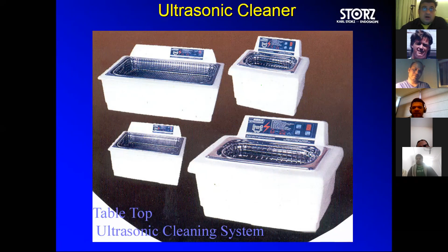Of course, there are ultrasonic cleaners now available. One can use them. Please mind you, these ultrasonic cleaners vibrate at a frequency. The water or disinfectant solution vibrates at almost 50,000 times a second to disintegrate the blood debris. Mind you, please never ever use the endoscopes or the camera heads inside this. Why? You saw in the video, in the endoscopes there are rod lenses at a certain distance, and there is a metal spacer to maintain the air gap spaces. If the endoscope vibrates like this, these air gap spaces can reduce and you will not get good clarity. So the rigid rod lenses, the fiber scopes and the camera heads are not supposed to be cleaned in the ultrasonic cleaner. However, all other hand instruments can be cleaned with these without any problem.